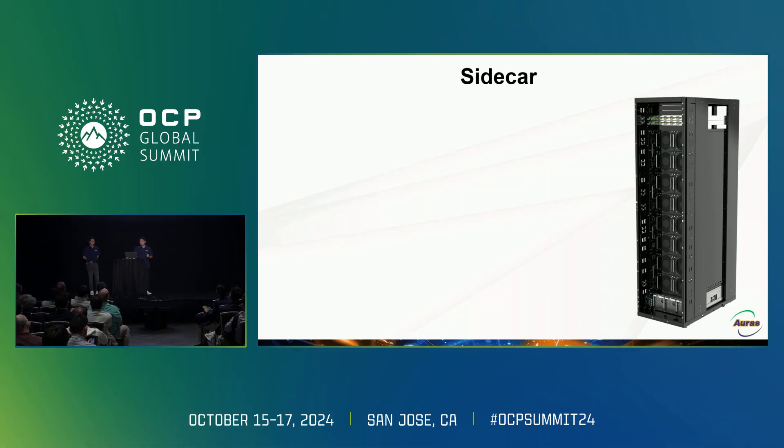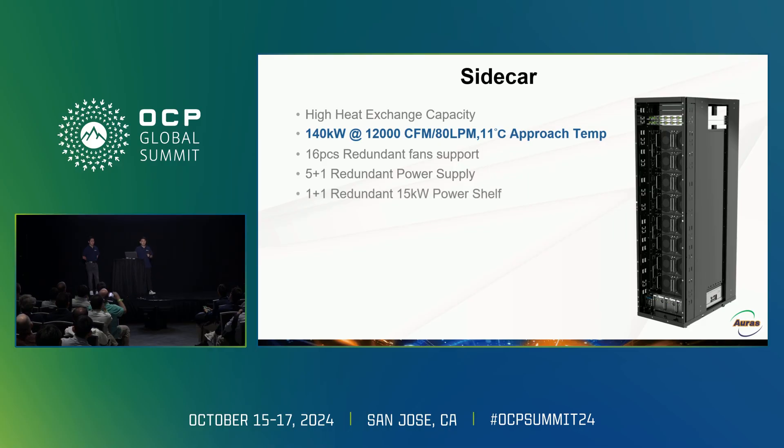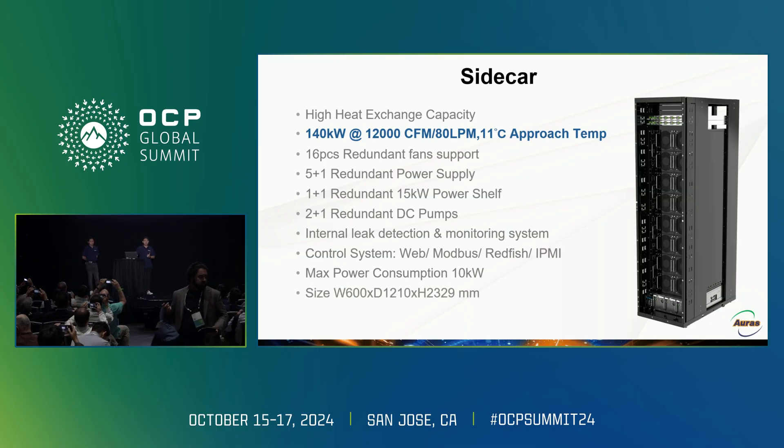Let me move from the component level to the system level. I'd like to introduce our high-performance heat exchanger product: the sidecar. It provides 140 kilowatts of cooling capacity, 12,000 CFM, and 80 lpm with an 11 degrees Celsius approach temperature. It has 16 redundant fans, 5+1 redundant power supply, 1+1 redundant power shift, and 2+1 redundant DC pumps. It also has an internal leak detection and monitoring system. The control interface includes web, Modbus, Redfish, and IPMI. Power consumption is 10 kilowatts.